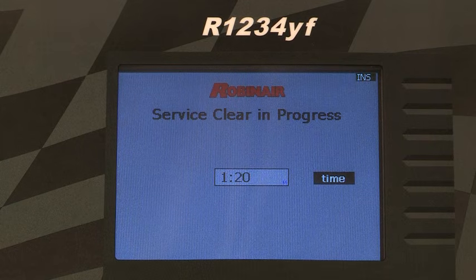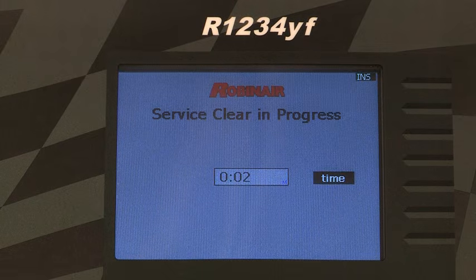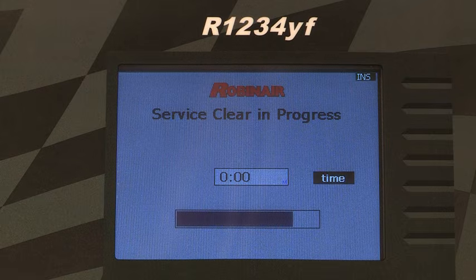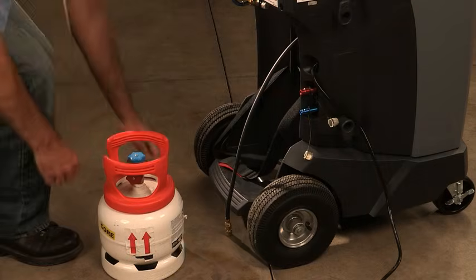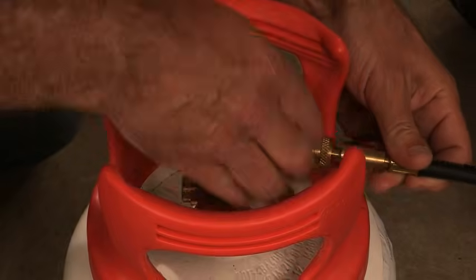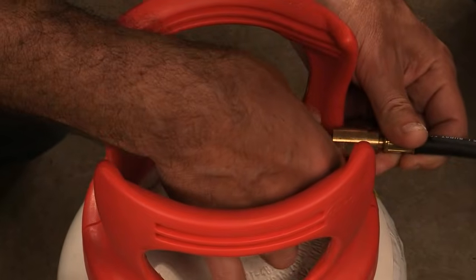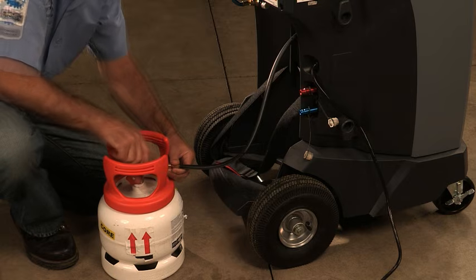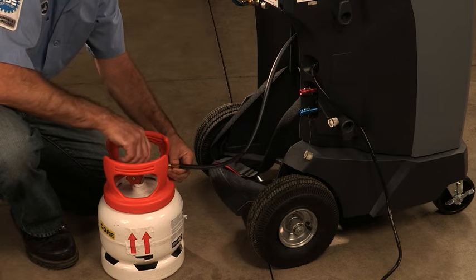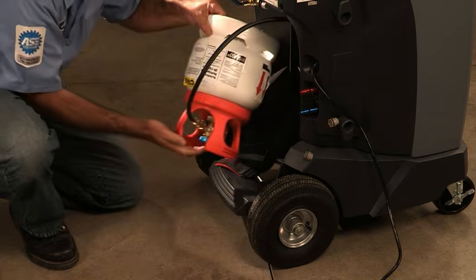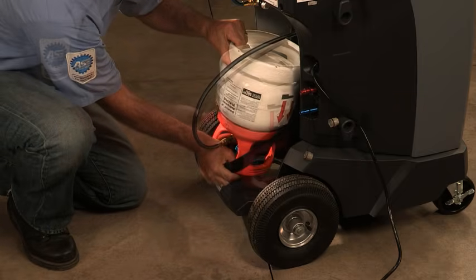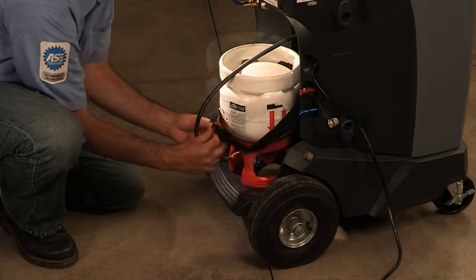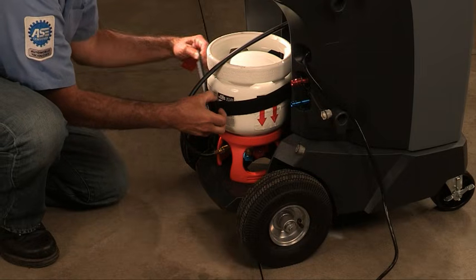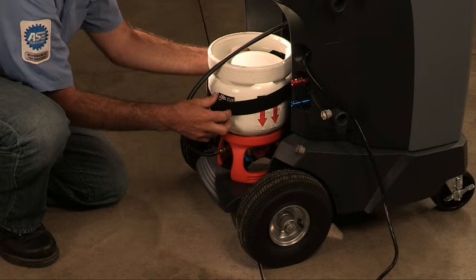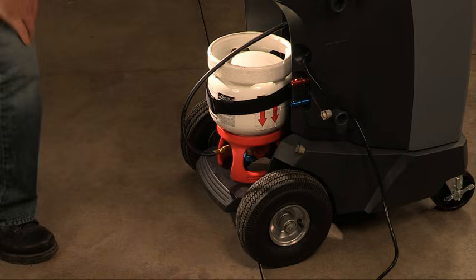It will sound an alarm when the tank fill adjustment screen is displayed. After the tank clearing process is done, you will need to fill the internal tank. Connect the tank fill hose to the source tank fitting and open the tank valve. In order to fill the internal storage tank, you need to position the source tank on the rear of the machine so the liquid refrigerant is supplied to the connection. Use the strap shown here to secure the tank in place. Be careful not to block the vents on the lower right side.